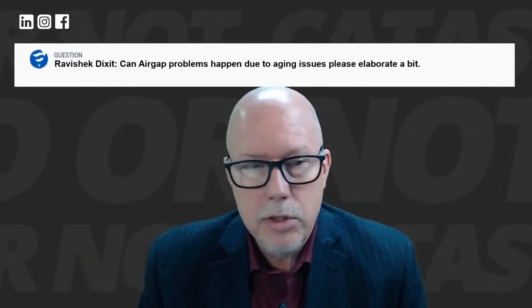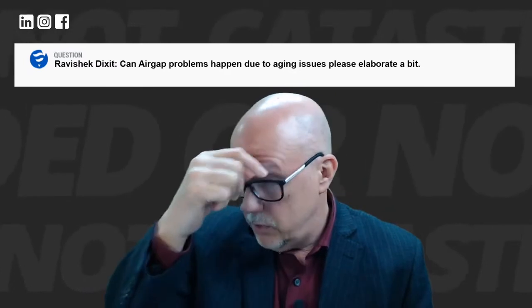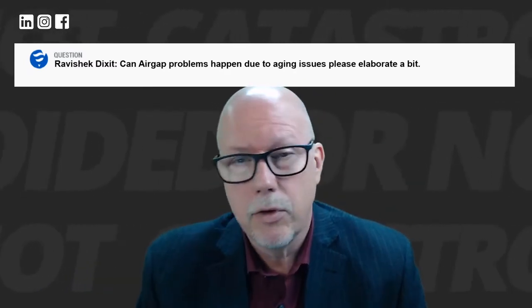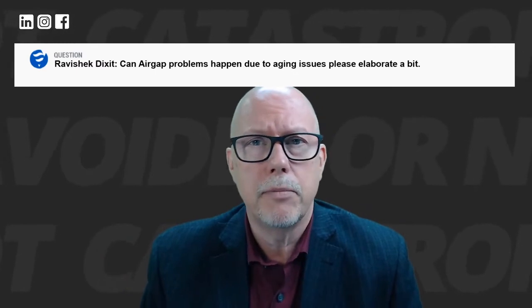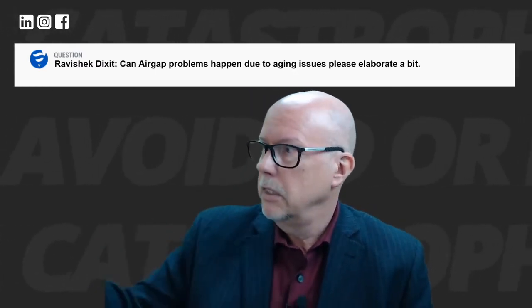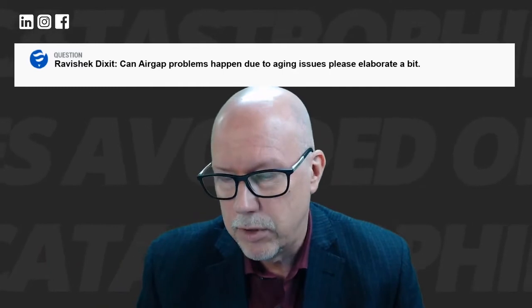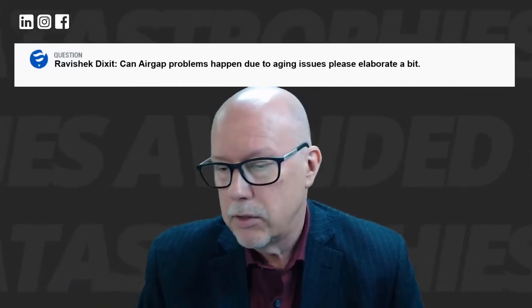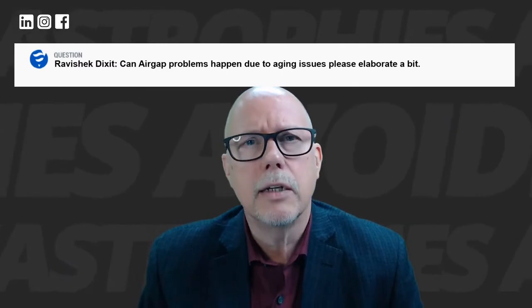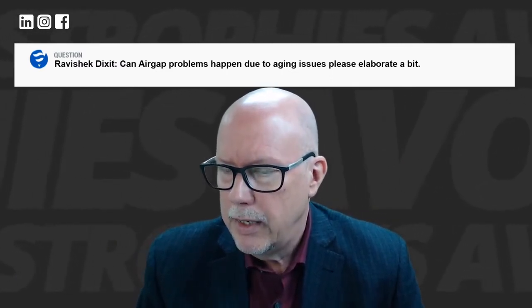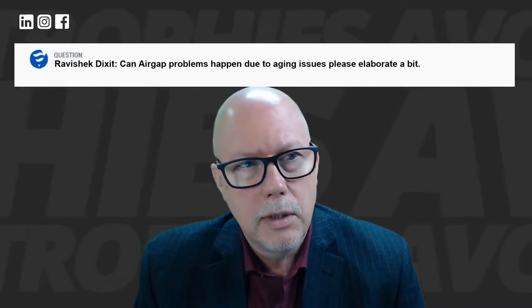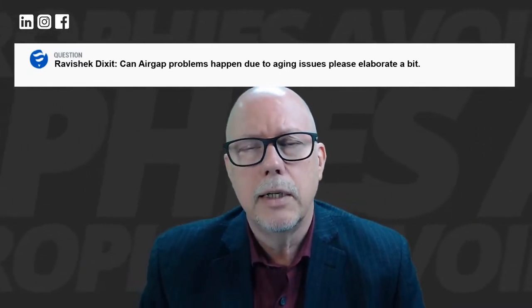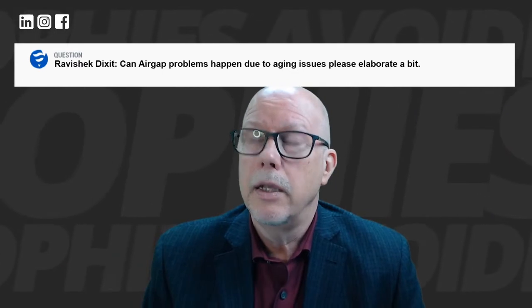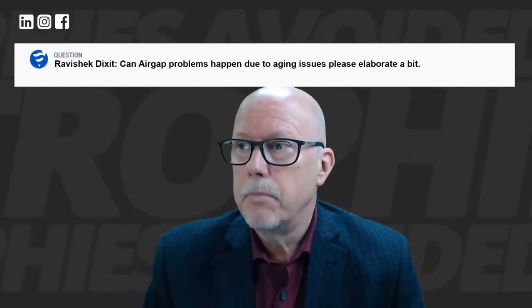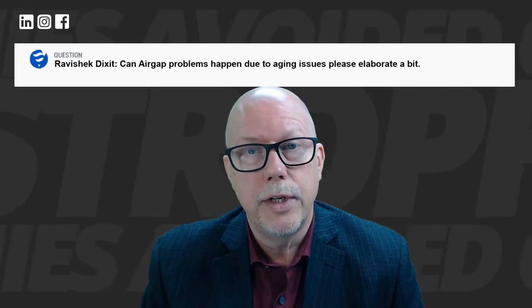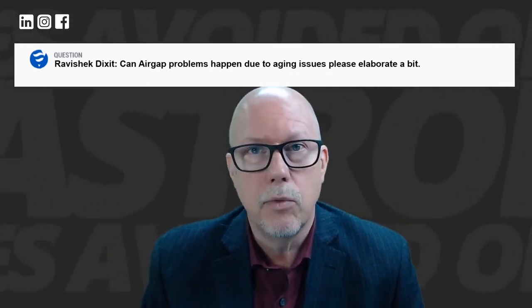This customer had a contract with VibroSystM, which had been collecting data on their units for a long time. Rather than take the rotor apart, which would have meant at least two months of additional outage plus repair costs, they asked us to check if this was really an issue. It turned out we had data on this unit going back to 1999, and we were able to quickly show them that, yes, the rotor shape is horrible, but it hasn't changed in over 20 years.